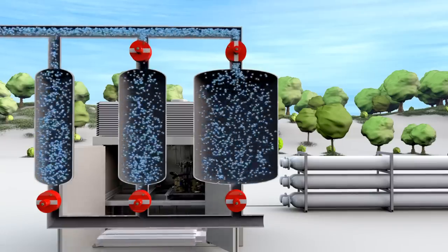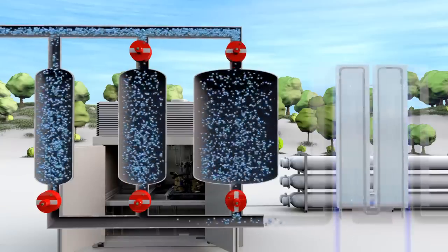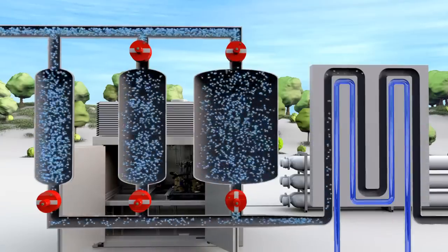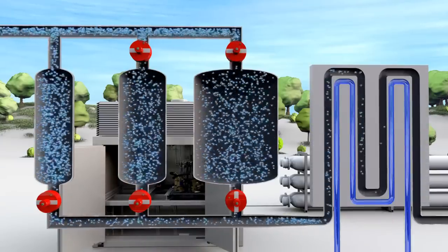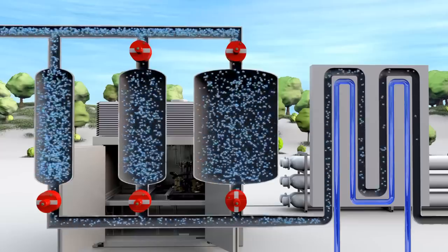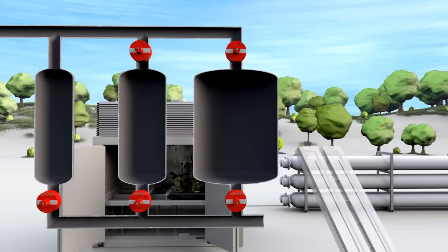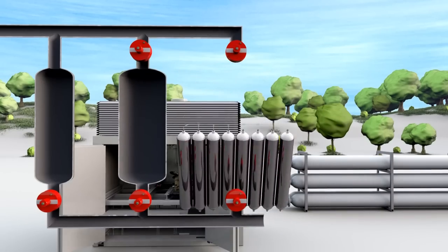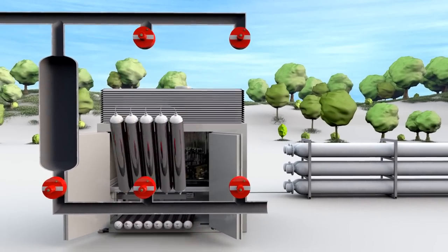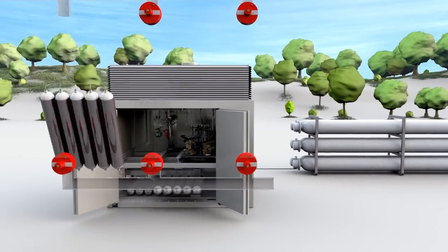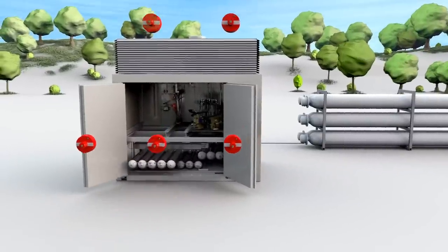Once the vehicle fueling process is started, the hydrogen flows from the high pressure storage through the Linde-developed aluminium cold-filled heat exchanger and is directly cooled to about minus 40 degrees Celsius. The aluminium cold-fill heat exchanger, in contrast to conventional liquid cold-fill units, is maintenance-free and can be cooled to even lower temperatures if necessary. Cooling the hydrogen is necessary to enable refueling in less than 3 minutes.